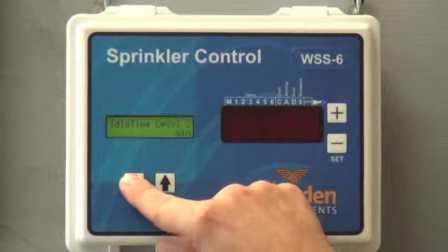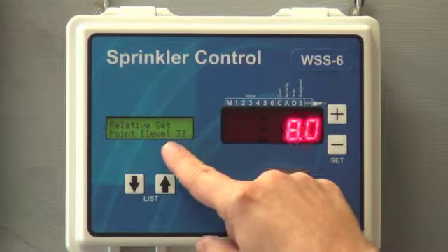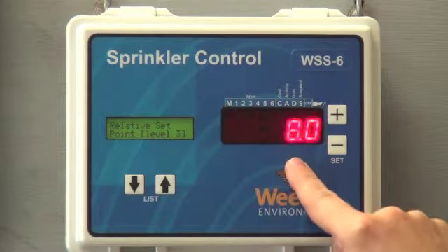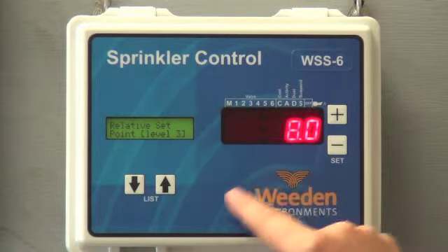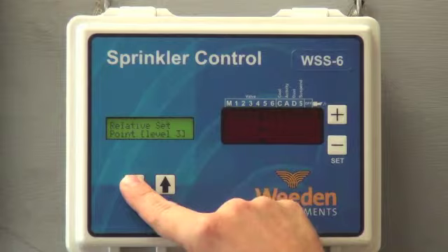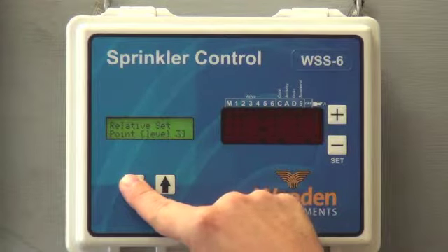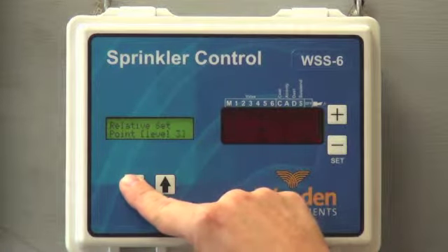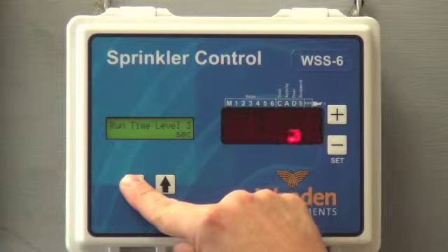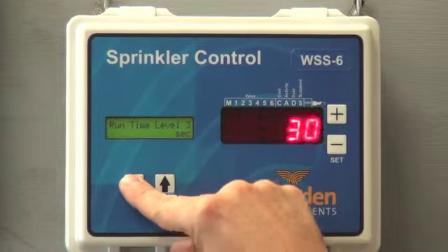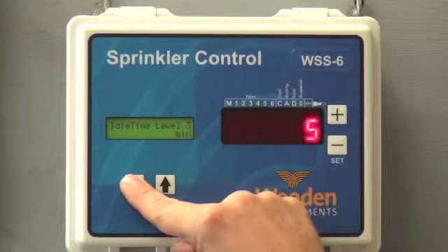Now let's move to the third level of cooling, which is our relative set point level number 3. That's 8 degrees above our set, which is 94 degrees in this example. Okay, so if it hits 94 degrees inside that poultry barn or poultry house, it's going to run 3 seconds, so the duration is slightly longer, and it's actually going to run every 5 minutes.